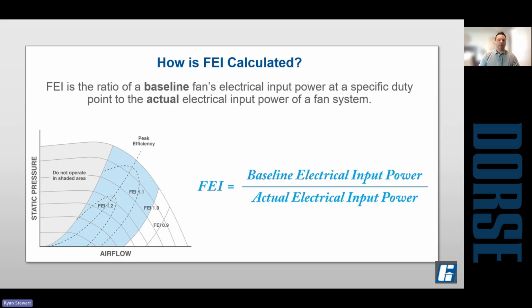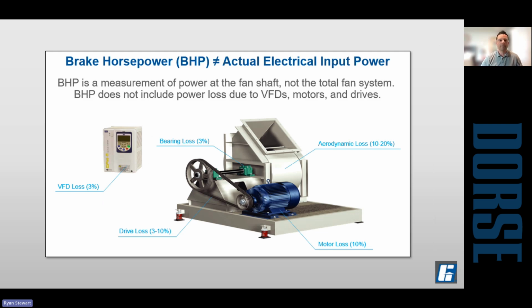So what is it and how is it calculated? They're looking at a comparison of a baseline fan's electrical input at that duty point to the actual electrical input for the whole fan power system. What you'll see there is a fan curve down on the bottom left, and you can see fans that are in the peak part of that curve are going to have the higher FEI rating. Typically lower RPMs are going to net a higher FEI. This is in comparison to brake horsepower, which is measured fan power at the shaft but not for the full system, so it didn't include the loss from VFDs, motors, and drives.